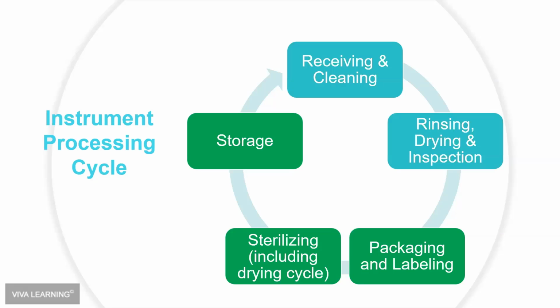The steam, or if you're using unsaturated chemical vapor for sterilization, the steam and the unsaturated chemical vapor must actually contact or touch all the surfaces of the instrument, and they can't penetrate through blood or debris on an instrument. So if you have instruments with debris, even if it's cement, doesn't even have to be blood, then that surface underneath won't be sterile. Then the other steps are packaging, labeling, the actual sterilization cycle, and storage.